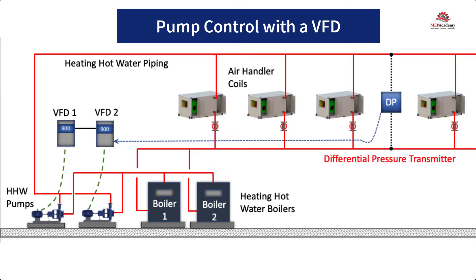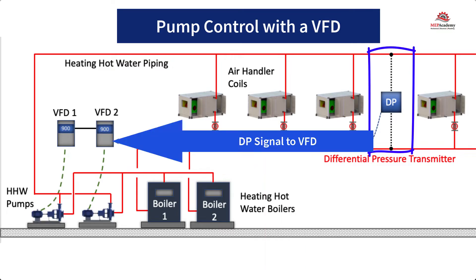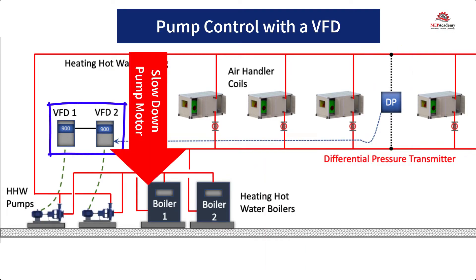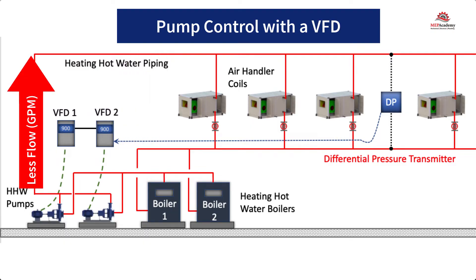The opposite happens when the heating hot water valves start to close because the space is warm enough. The valves start closing, causing an increase in pressure in the piping, which is sensed by the differential pressure transmitter. The transmitter then sends a signal to the variable frequency drive to slow down the pump motor, reducing the flow, the GPM.